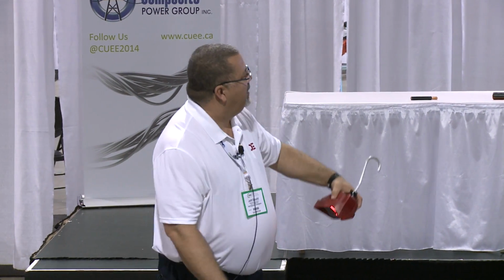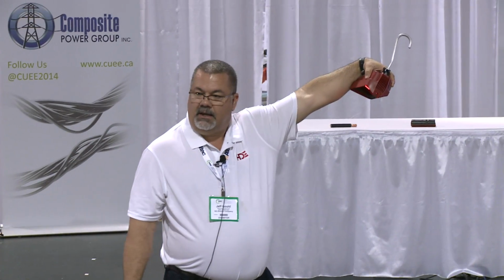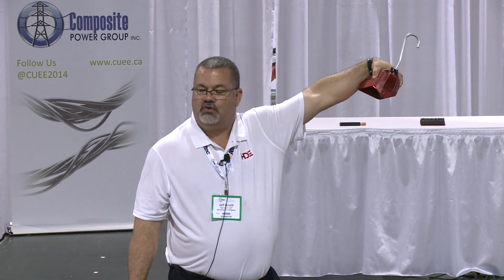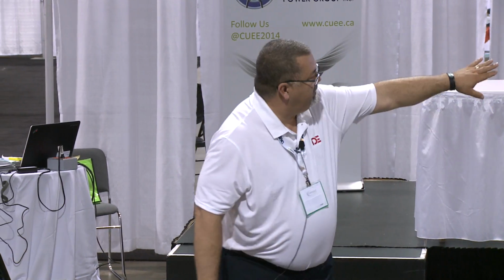And one of the ways that you will understand that if you're using this device is when you're in that electric field, whether I have a display on the front of the unit or not, it will already be beeping at you to let you know, hey, I'm in an electric field, something around me is energized. But it won't actually give me a reading until I contact the actual conductor. It won't electrocute you? It will not. That's correct, because we're on the end of a hot stick here.